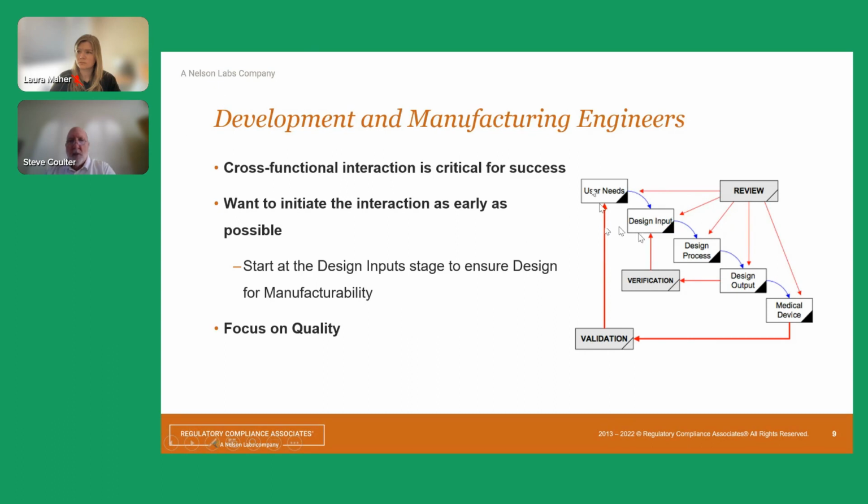The sequencing is critical. You can't start a project without establishing design inputs and user needs. User needs, what the actual user, whether it's a patient or whatever, needs, that's only one of the things that goes in the design inputs. Manufacturing requirements and regulatory requirements also go in there. So all the way back here, we're doing all of the data mining to figure out what we need in our inputs. That's why I say this is critical, that we get manufacturing engaged back here.